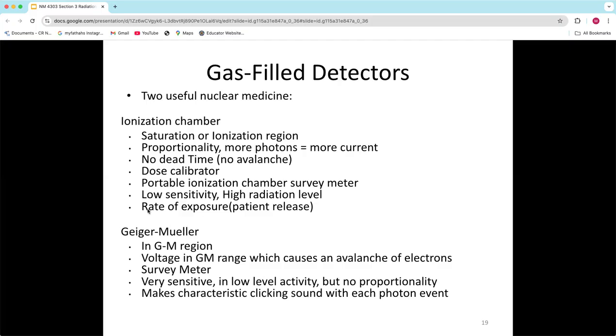And remember, you're going to get a rate. So they're not as sensitive. They're made for higher radiation doses, and it's for rate. So again, think anytime I'm needing to get a rate or a measurement on something, that's when I'm in that ionization range and using it as an ionization chamber.